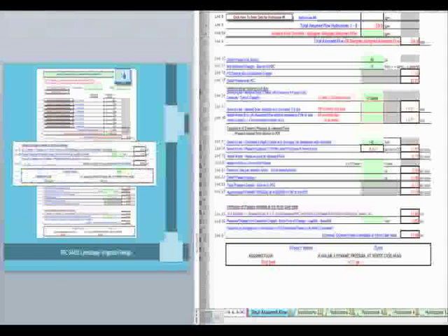In the last section, we estimate the pressure available at the worst case head. So that's very similar to what we did with design with the metered municipal system. So here, line 25 is a 2/3 estimate. It assumes 1/3 loss of PSI between the point of connection and the worst case head. Right now, that has determined that it's 51.68 PSI. So it took this line 24, multiplied it by 2/3, and ended up with 51.68 PSI.